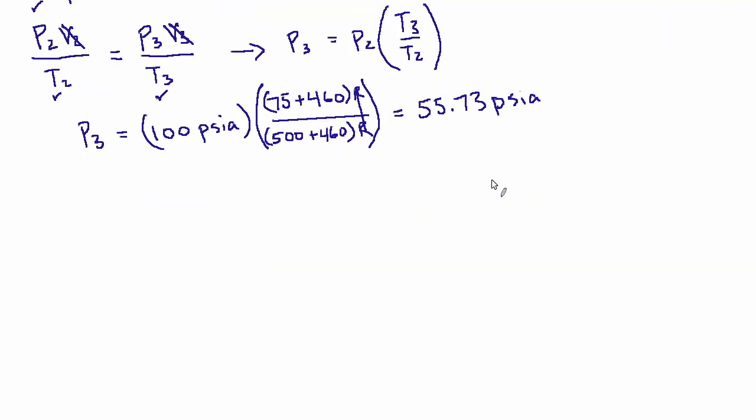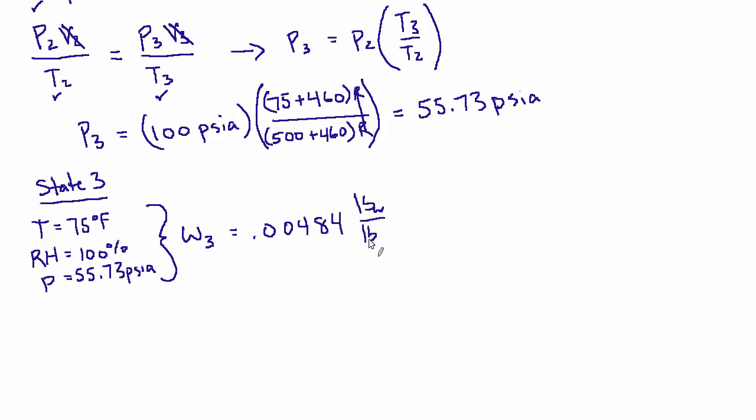So now what do we know about state three? We know three things. And I'm going to do what I did before and use those three things to use the psychrometric calculator and get the answer first. And then we'll do it some manual way. So after we get an answer, we can check it against what the psych calculator said. So let's restate what we know about state three, 75 degrees Fahrenheit, a relative humidity of 100% because it's saturated. And we just found the pressure to be 55.73 PSI. So based on those three facts, we can plug it in and get the humidity ratio, which is 0.00484 pounds of water per pound of dry air.